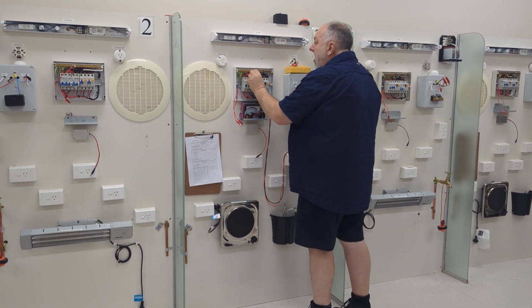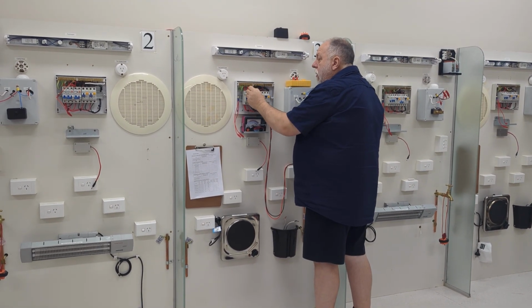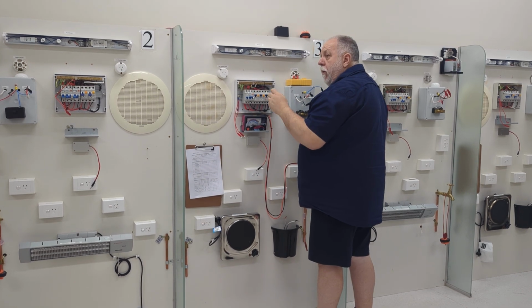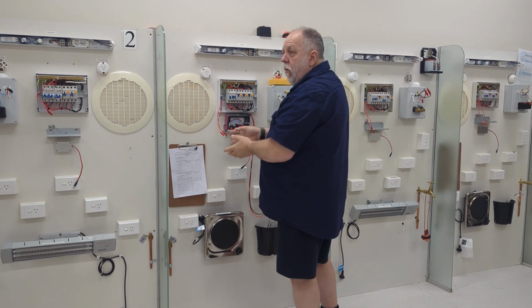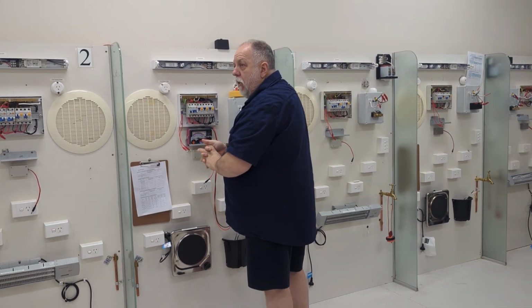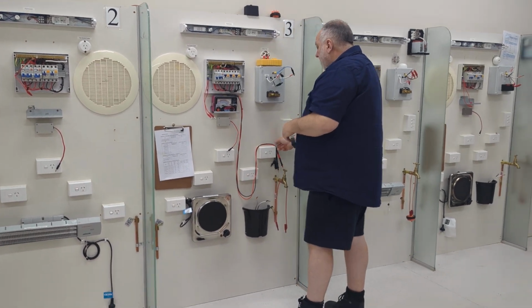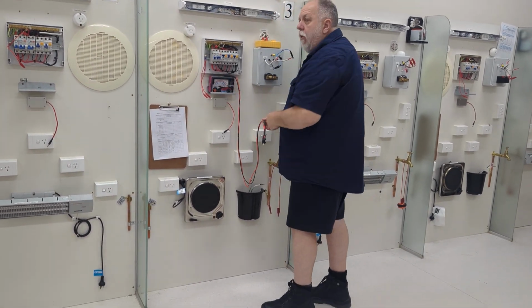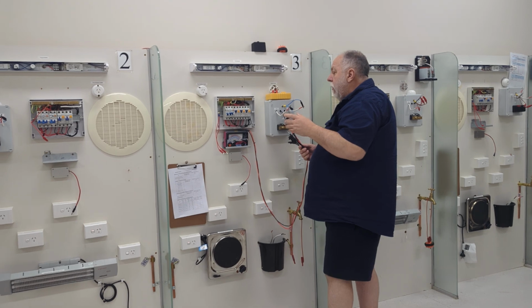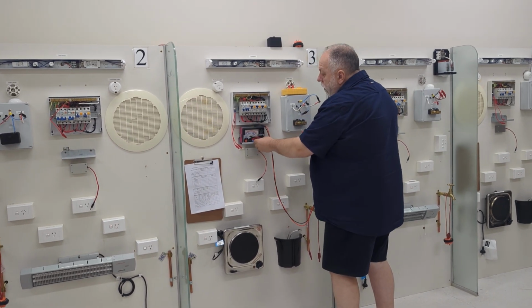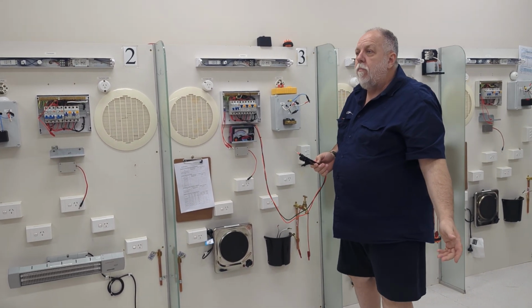At this point, if I had my MEN in, I would disconnect it, which I have to do, because now we're testing active and neutral to earth, the insulation value. Now, before I did the zeroing on the ohms and all that stuff, when you select 500 volts, do I select 1,000? Why?